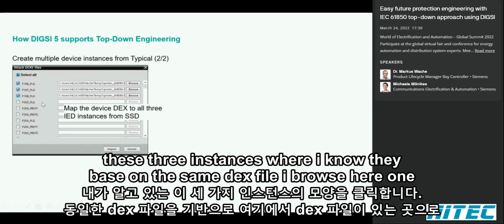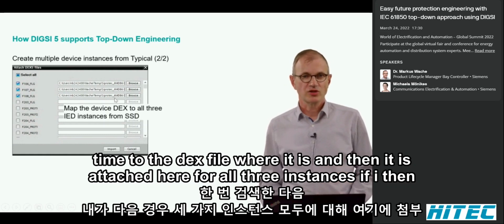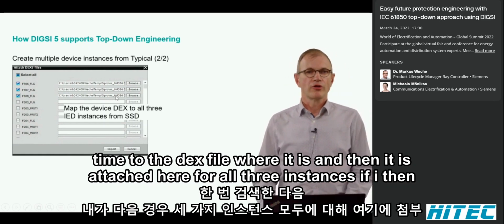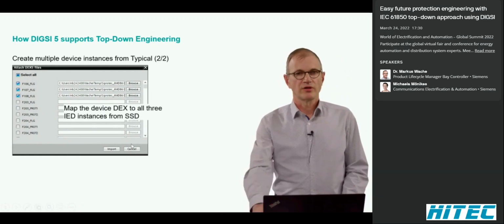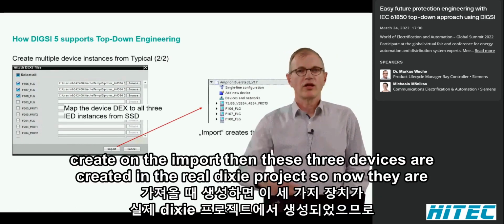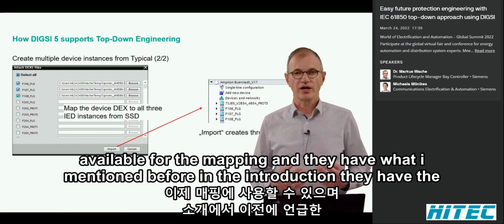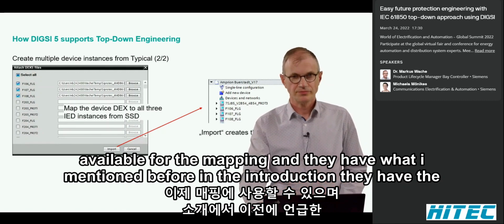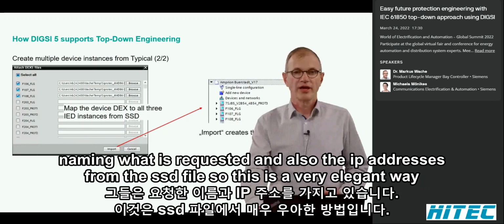So I click on the appearance of these 3 instances where I know they are based on the same DEX file. I browse here one time to the DEX file where it is, and then it is attached here for all 3 instances. If I then create on the import, then these 3 devices are created in the real DIGSI project. So now they are available for the mapping. And they have what I mentioned before in the introduction: the naming, what is requested, and also the IP addresses from the SSD file.